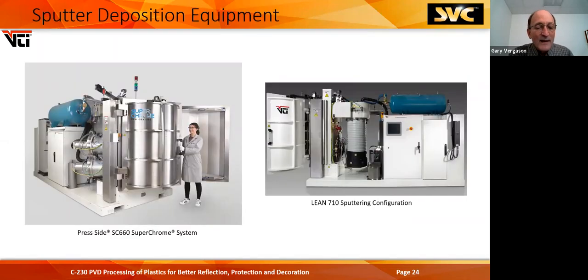Sputtering equipment can look a lot like the other filament equipment. This is our SC660 Superchrome machine. It's about 38 inches across the vacuum chamber. Again, we like to use the water traps and the dry air venting. High voltage power supplies are kept separate from the three phase, and they're kept separate from the PLC control bank.